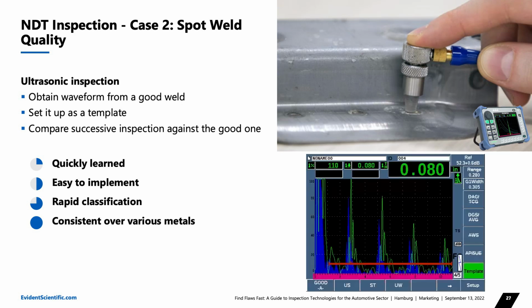You still have a signal bouncing back from the bottom of the weld, but because the weld structure is not correct, it's not the right grain structure, you do not have the same attenuation of the ultrasound, and the signal that bounces back is with a higher amplitude. So you can see here it's above the 100% high screen, and it's not supposed to be there.